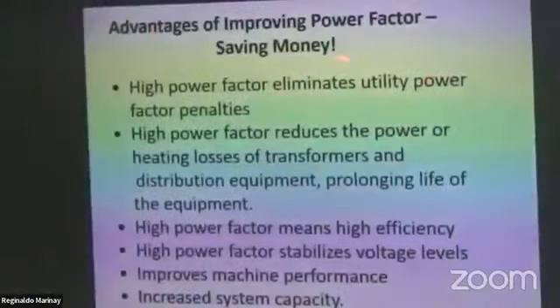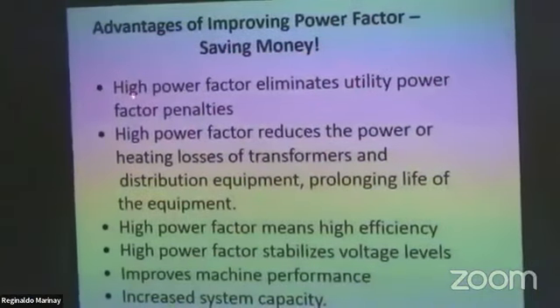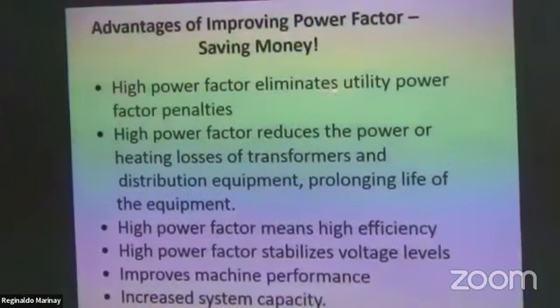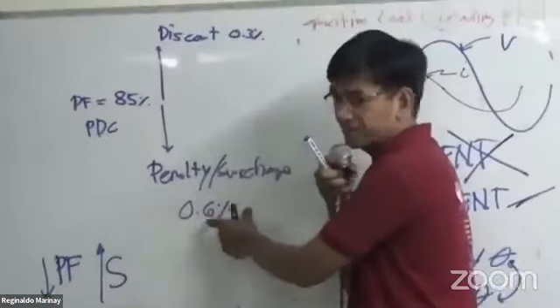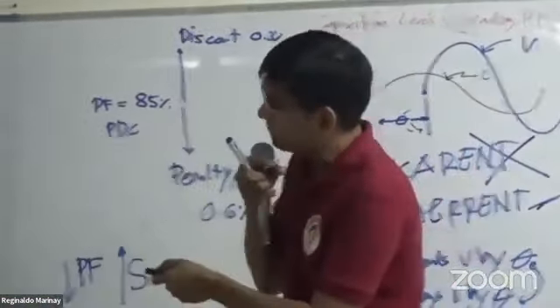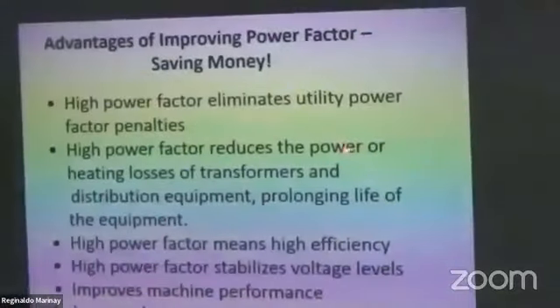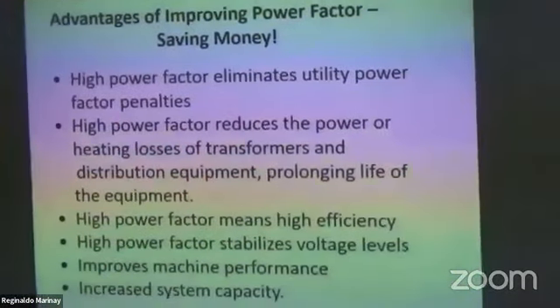So, advantages of improving power factor: saving money, of course, that's the most important contribution. High power factor eliminates utility power factor penalties - so there is a penalty here that can be eliminated. High power factor also reduces the power or heating losses of the transformer.